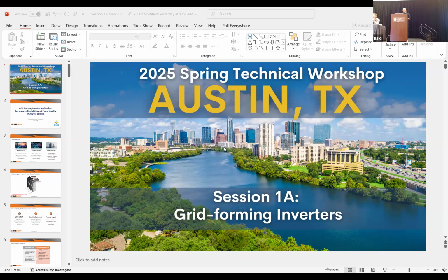One of the challenges for these AI-based data centers is the power quality. It is already observed that 2-3 years ago, when ChatGPT came into the market, around the neighborhood of the existing data center facilities, people started seeing their lights flickering on and off. It was at that time that people realized that something is off in terms of the computation of the algorithm for AI-based data centers. If you run crypto mining, or you just have a facility to store data, typically the consumption is constant, so you don't see that much variation.